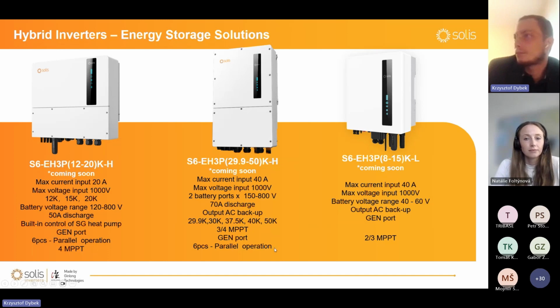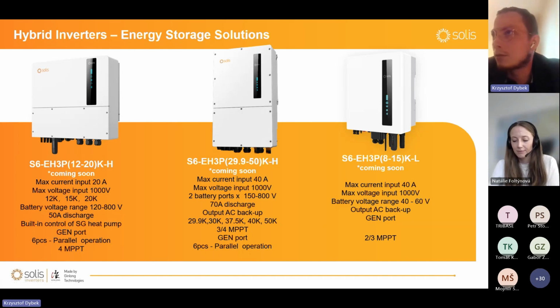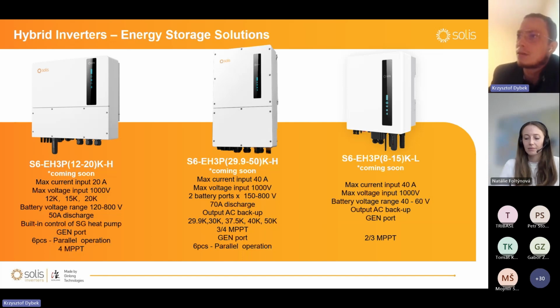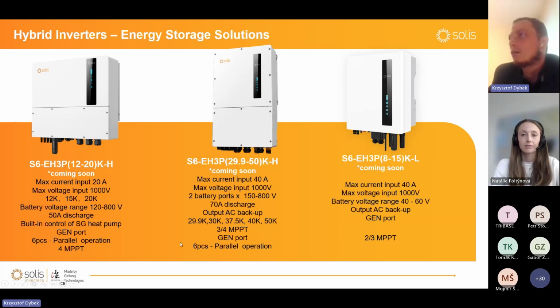So what can be said about this guy? Max current input is 20 amps. With the biggest, even 40 amps. Max voltage input is 1000 volts per MPPT. Battery voltage range is starting with 120 up to 800 volts, 50 amps charge discharge. Built-in control of SG heat pump. This is not ready just yet, but it will be ready very soon. Generator port. I will tell you more about it later, but it is a very interesting solution, I guess. And you can put 6 pieces of those in parallel operation. And this guy has 4 MPPTs.